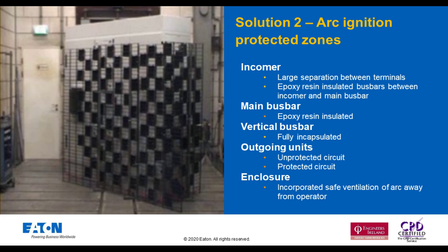So the next criteria is where personal protection and assembly protection is achieved. So this is criteria 1 to 6. And essentially criteria 6 is the assembly is capable of confining the arc to a defined area where it was initiated, and there is no propagation of the arc to other areas within the assembly. Plus the hot gases and sooting effects to adjacent units other than the unit that was under test are acceptable as long as only cleaning is necessary.